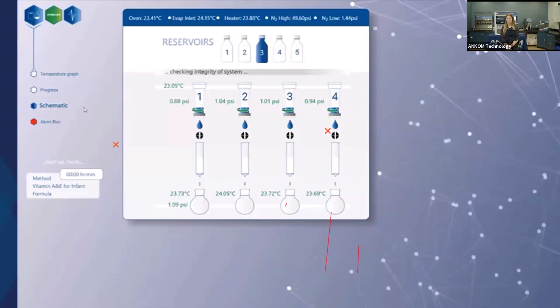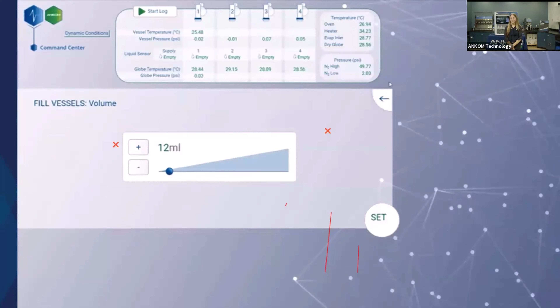The ANKOM Flex Analyte Extractor's software includes complete record keeping of all assays, faults, calibrations, and services. Short reports and raw data files can be downloaded for record keeping or further diagnostics. The Advanced Diagnostic Center allows the user to run diagnostic tests on the instrument to support troubleshooting and calibration. Once the user is ready, they can start the assay and walk away.